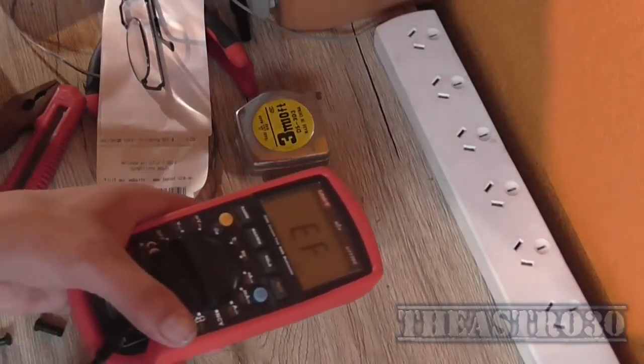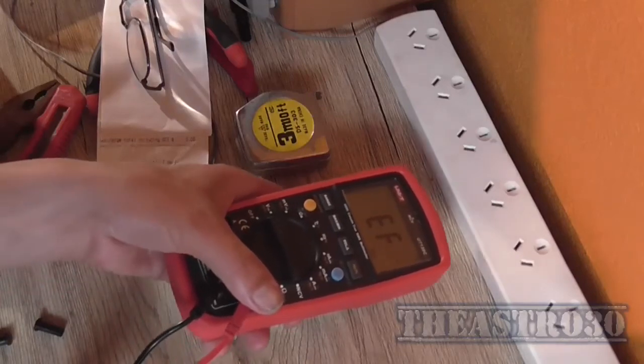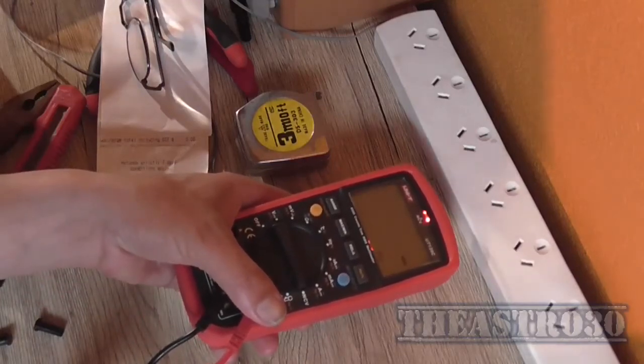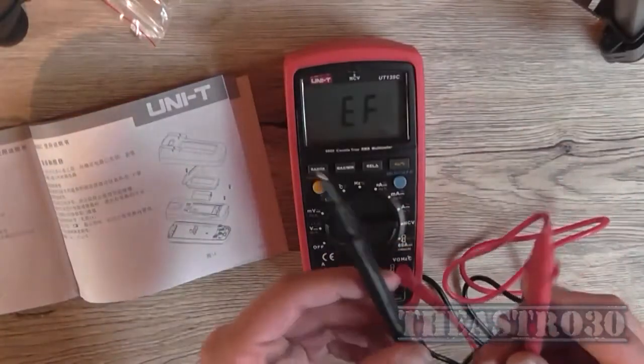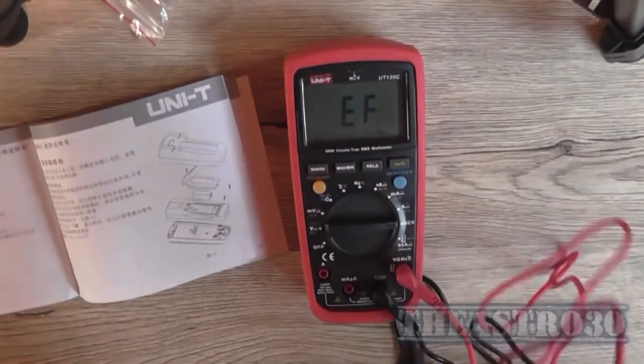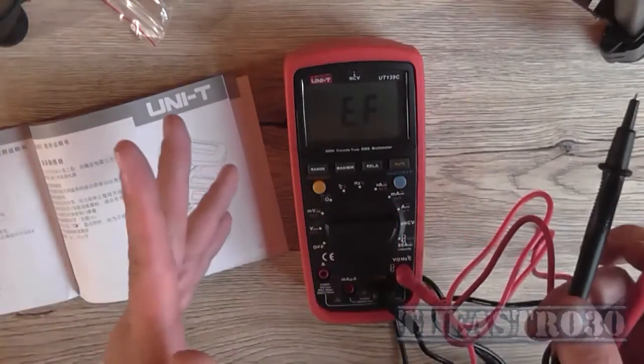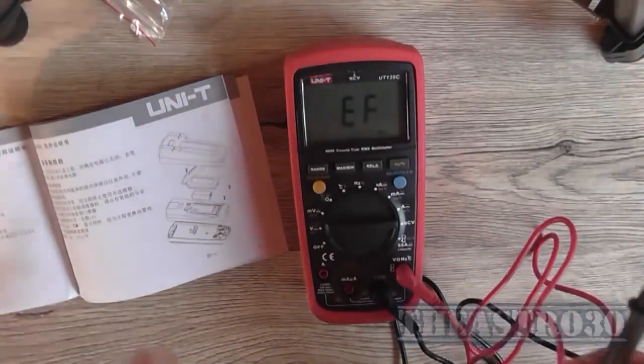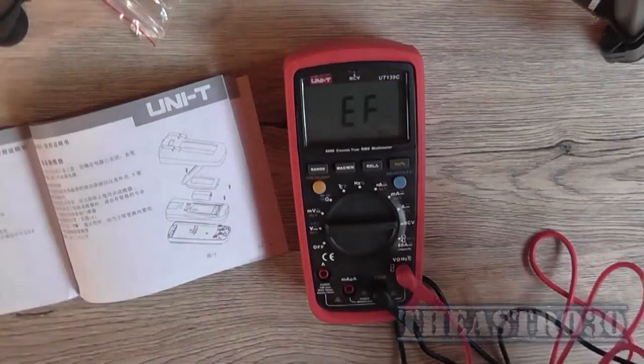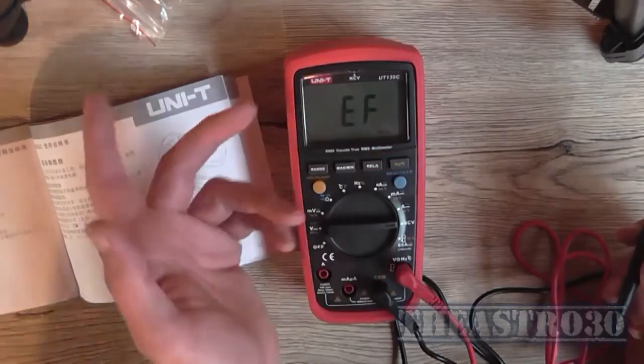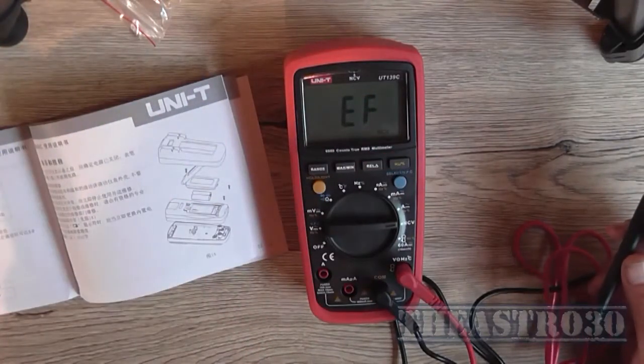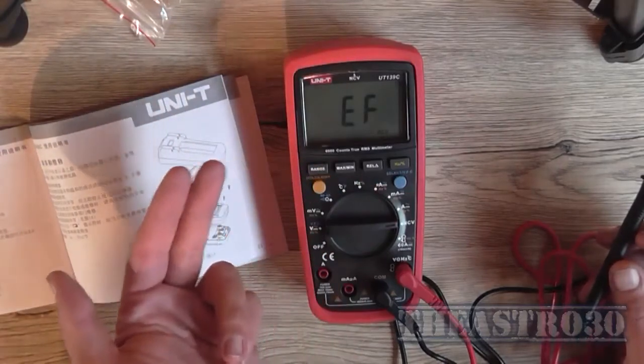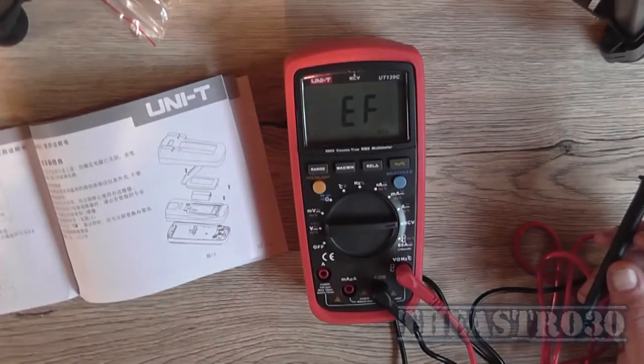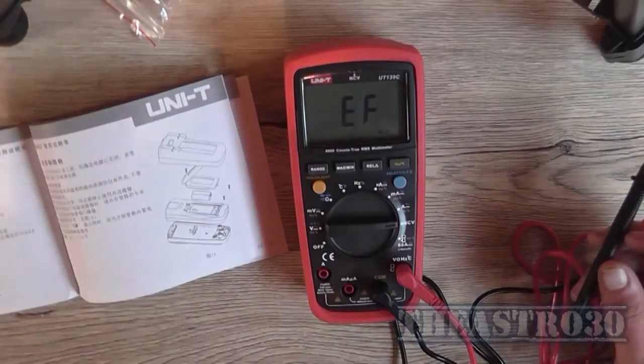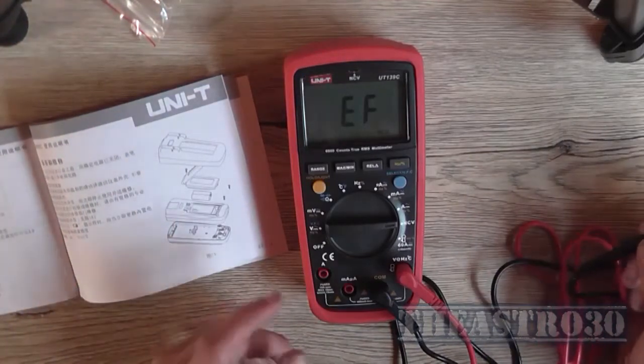So for example, it's telling me that power board is live. You can test to see if a wire is live, such as in your AC mains wiring in your house, or a light socket or power point, to see if there's voltage on the line. You can just hold it up to the socket and it will tell you whether or not there is power on that particular socket. That means you haven't isolated the circuit yet. That gives you the no go ahead to do any work on that circuit until you isolate it. So that's what that's for.